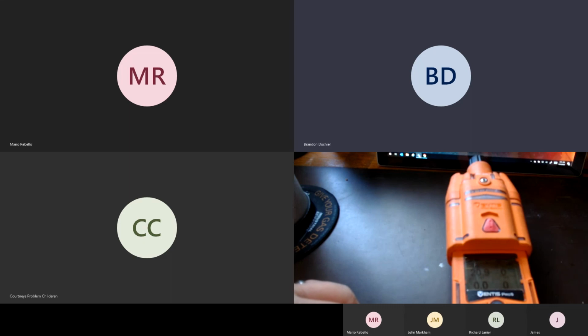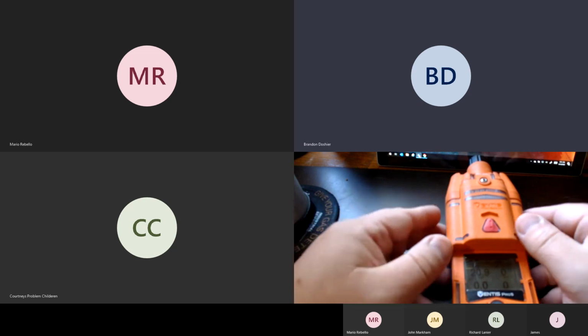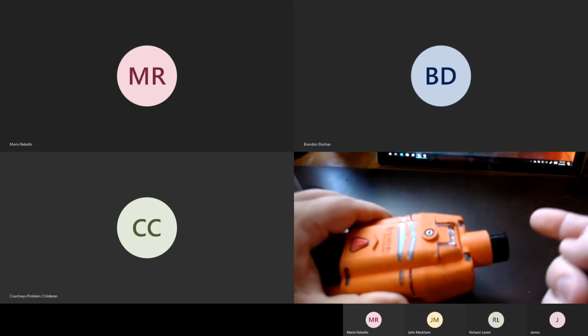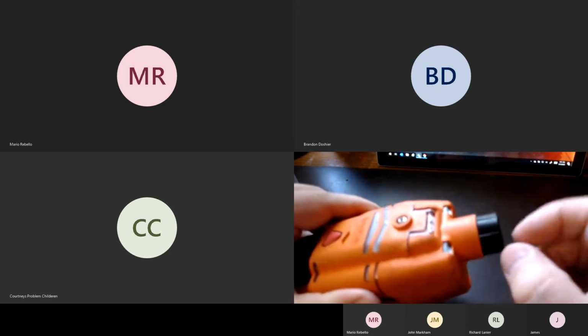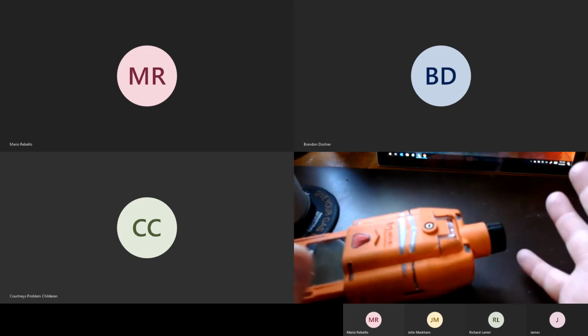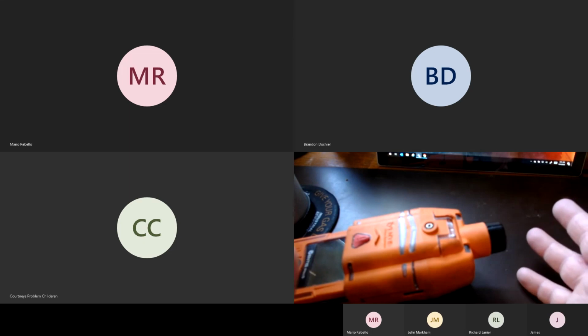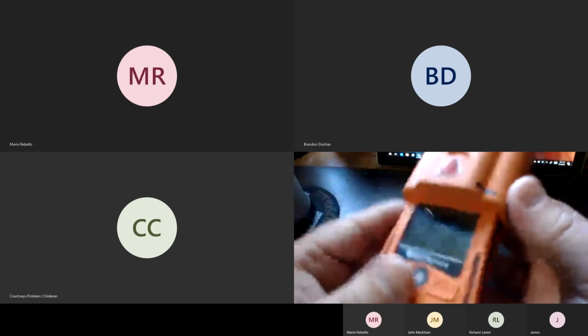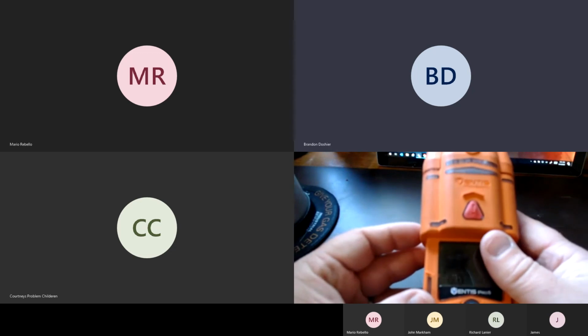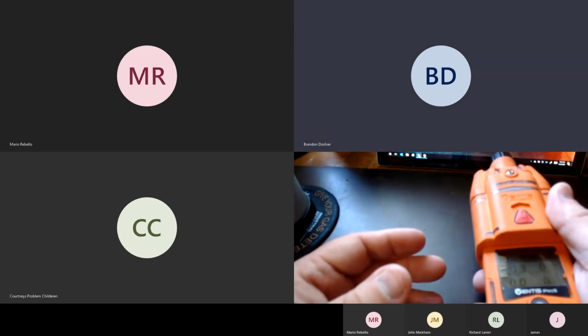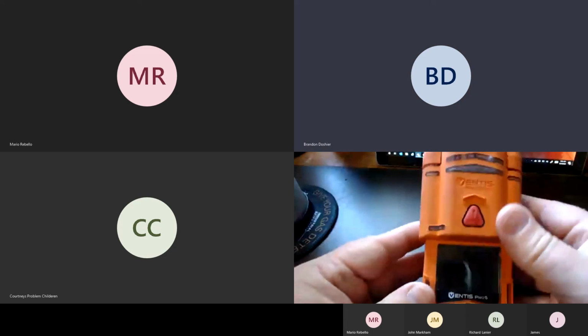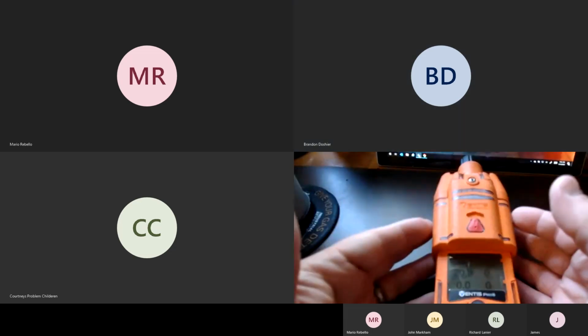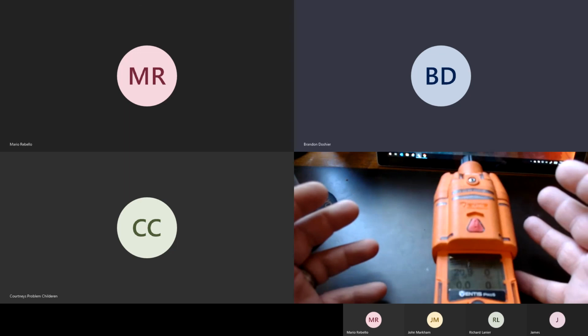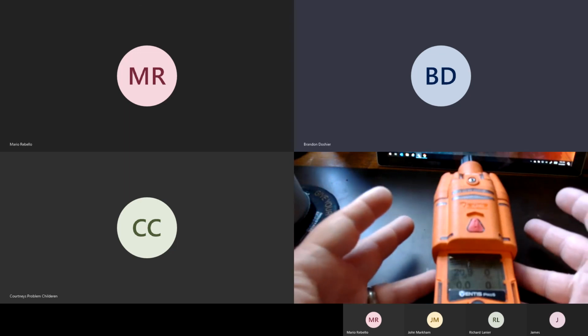Now the unit came with extra tubing. Is that to, if we need to go down a manhole or something to test the air? Correct. That is for confined space sniffing, and that will just connect on to the inlet up here. And then with that, you do have to do a little bit of math, okay? And that was the next thing I was going to talk about with these instruments, is when you're using the instruments with no tubing on here, say you're taking a reading, here's the thing. There's a lot of guys that still think that these things are instantaneous readers. As much as I wish that they were, they're not. Okay?